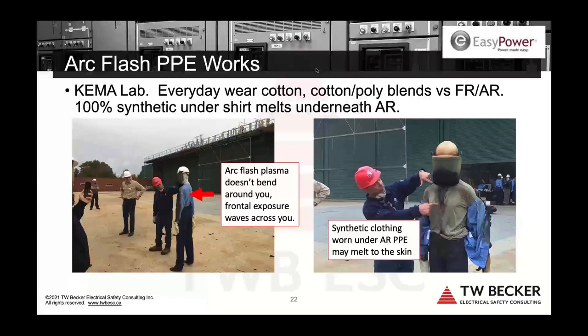Now, what's going on here is Scott Marzano with Tyndale is pointing to meltable clothing worn underneath. So arc flash PPE works, but we've got to get natural fiber clothing worn underneath. So again, here are the pictures. Here's the evidence. I was there. I witnessed it. All of these studies, following the energized electrical job workflow, are to get the worker to wear this arc flash PPE when they're exposed, and it works. And we need to tell them that it works. The results look horrendous, but the design is for a 50% probability of the onset of a second-degree burn injury when they're exposed at the ATPV of the clothing they're wearing.